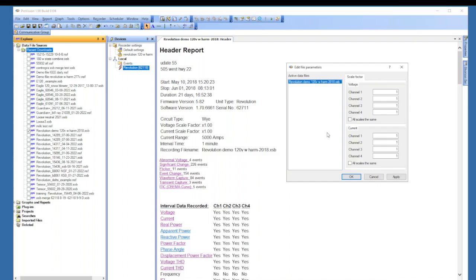If you happen to open up your real power and you notice that you have negative real power, that is one clue that your Flex CT is on backwards. It could also mean that you have solar and/or some other generation that's putting out more than what they're actually using. But if it is a Flex CT or TLR on backwards, all you have to do is go in and put a minus in front of that current channel, and then click OK, and it will save it to that data file. So even if you sent that data file to someone else, that setting would be in there.